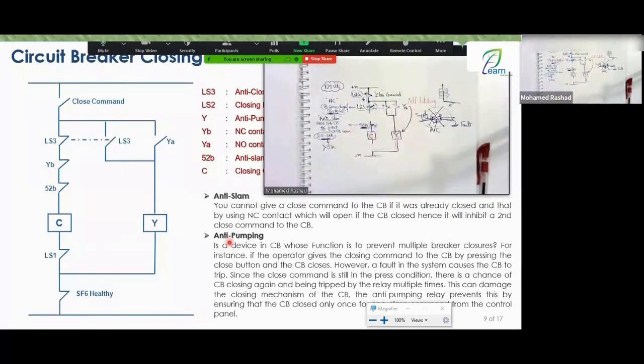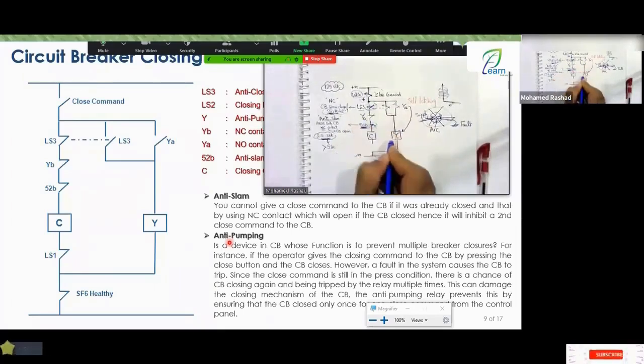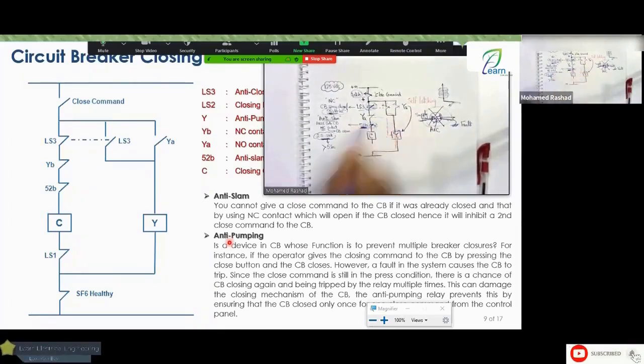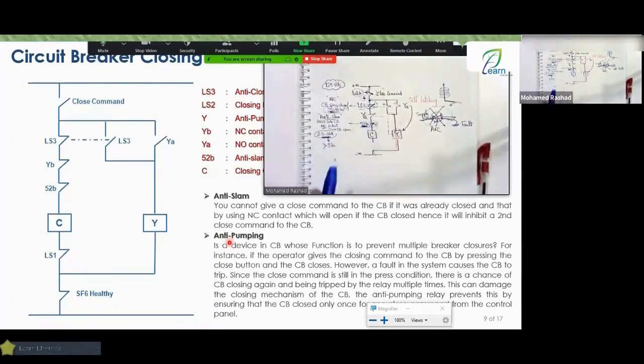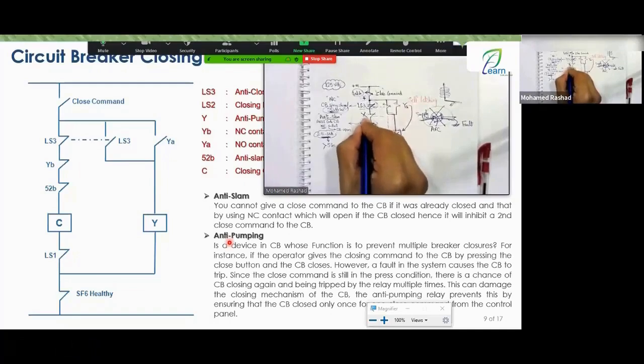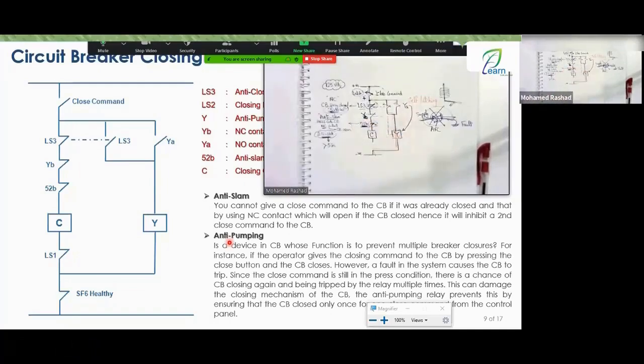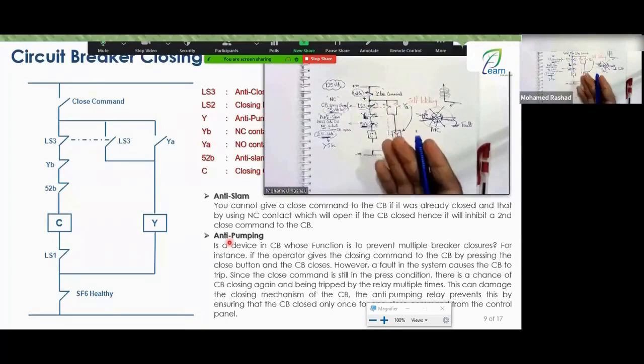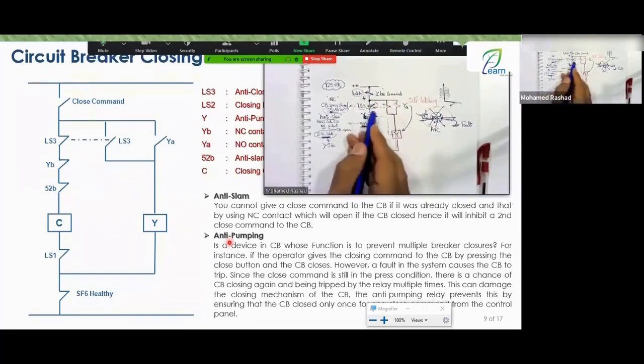So it comes here and takes a normally closed contact from this Y like this. A normally closed contact from this Y, is it like this? So I made this dotted plan, meaning that this is part of that. And it takes a contact here called YB, for example. Great. It takes YB. So as long as this is working, it opens the path here. As long as the DC is hanging here, this path remains open. So even if the breaker closes on a fault and opens, and this returns to close, and this returns to close, the path is cut off through this. This is called anti-pumping.